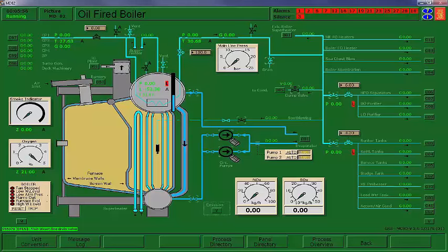We're not going to run the circ pumps. We have no waste heat. We're not going to be running that system. But again, on the initial lineup of this boiler, I would open the inlet and our return to prevent us from forgetting those as we move down through the exercises. All right, so we're ready to light.